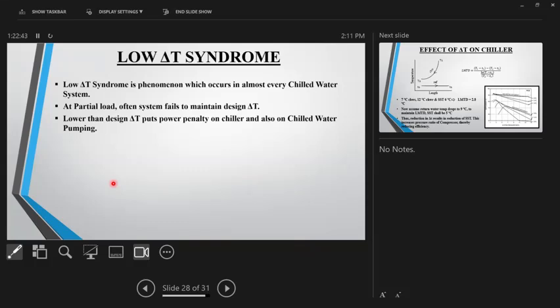So basically, low delta T syndrome has two ill effects. It forces you to overpump, and overpumping is obviously excess power spent on the pumping system. And due to overpumping, you need to fire the chillers to satisfy the flow and not to satisfy the load. So this is the problem. Ideally, the chiller should switch on and off based only on load. But if it has to respond to flow to start or stop, that is a major inefficiency. We'll talk about that in the next slide. So low delta T syndrome means overpumping and also extra chiller power.